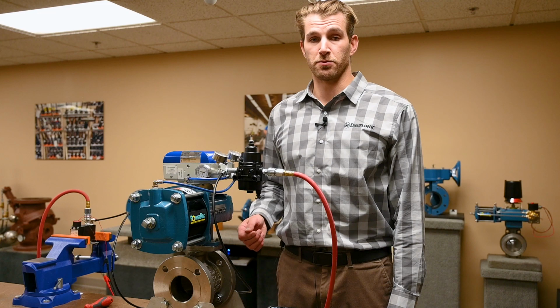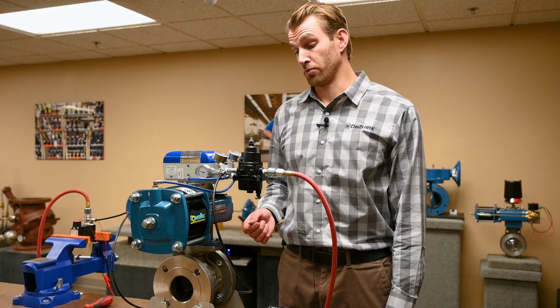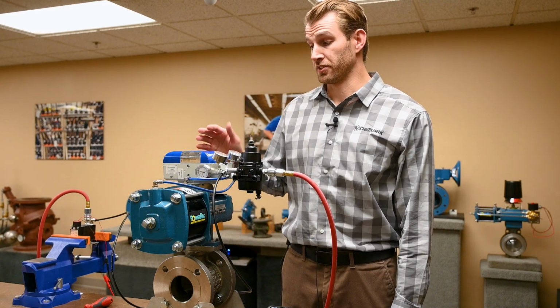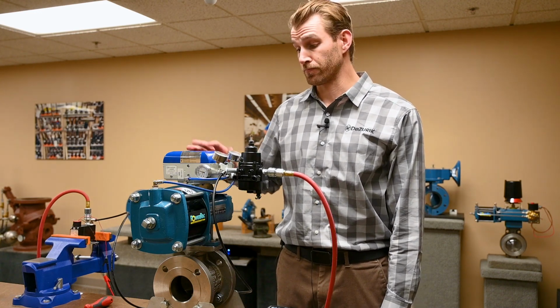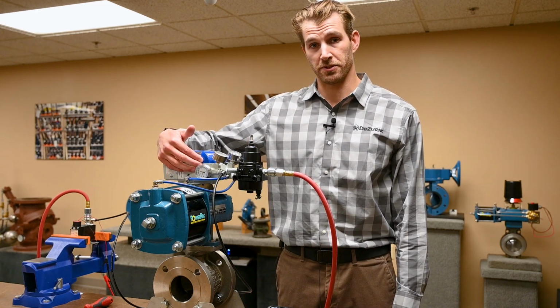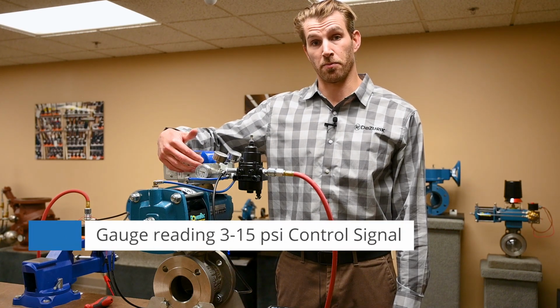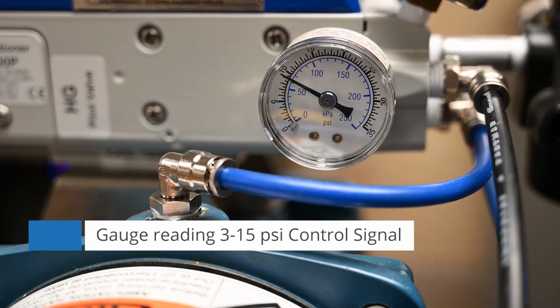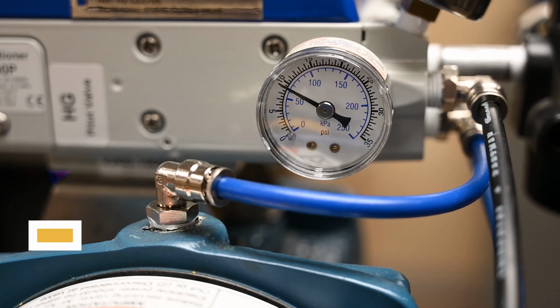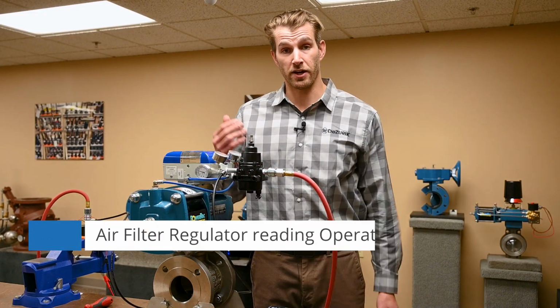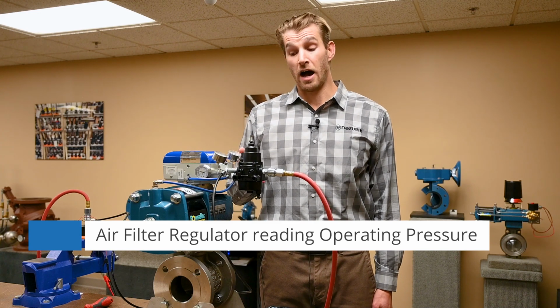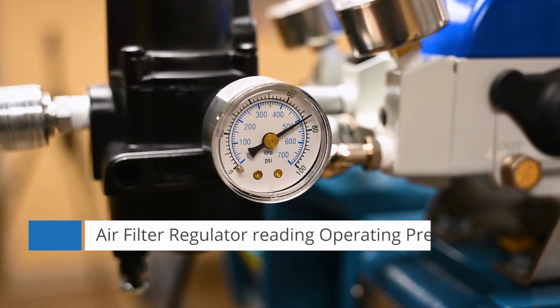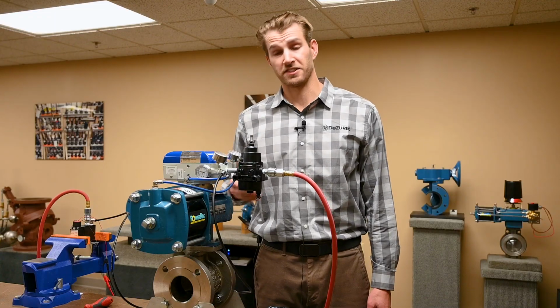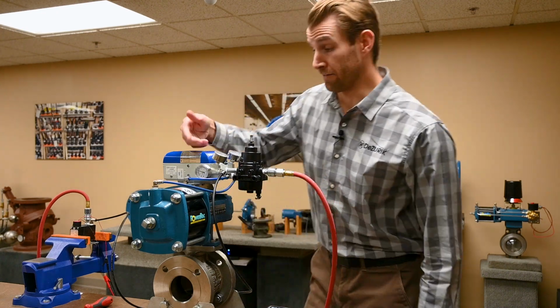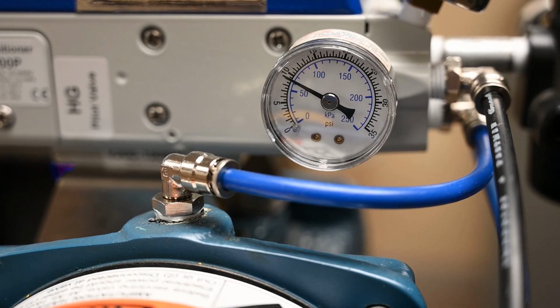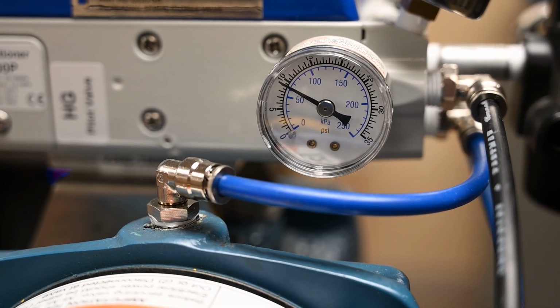To help illustrate the difference between the operating pressure and the control pressure, we'll use the gauges on this P200 analog positioner. The gauge located on this side of the positioner is what's reading the 3 to 15 psi control signal that is being received, whereas the gauge that's on this air filter regulator is reading the operating pressure that is being received somewhere in the plant. In this case, it's set to 70 psi, whereas at 50% open, you can see it's approximately a 9 psi signal being sent to the positioner.